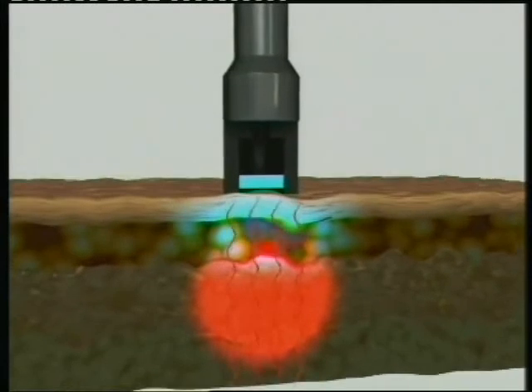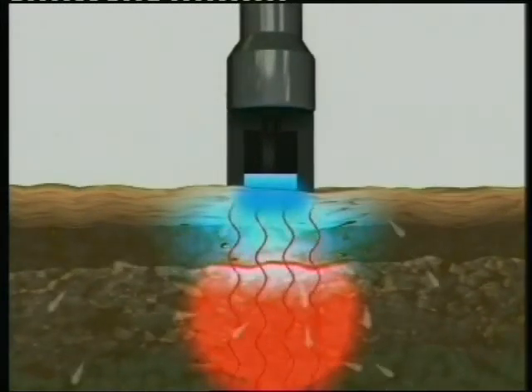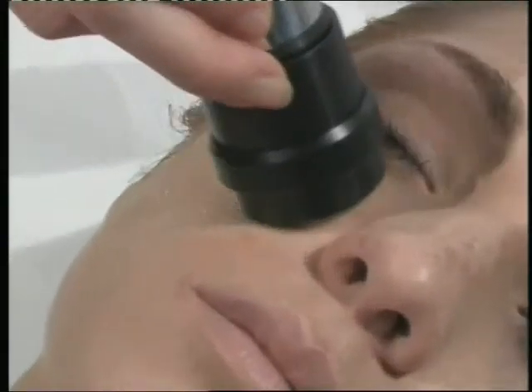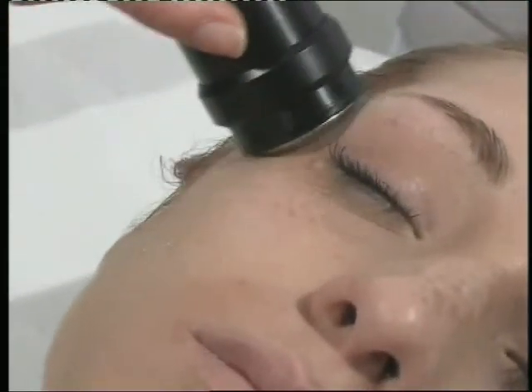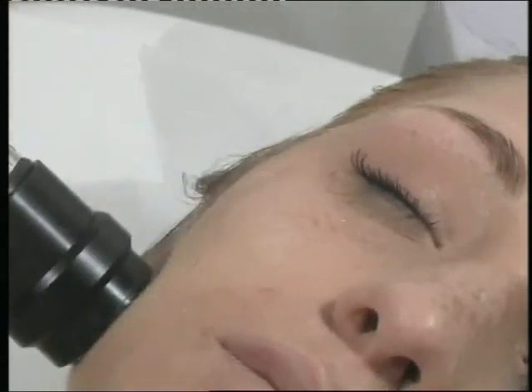The bipolar handpiece penetrates less deeply into the tissue. It uses vacuum to fold the skin, ensuring tight contact and positioning the dermis in direct alignment with the path of radio frequency. The combination of this vacuum positioning and the cooling medium concentrate heat in the dermis, sparing epidermal tissue and leading to collagen contraction and regeneration.